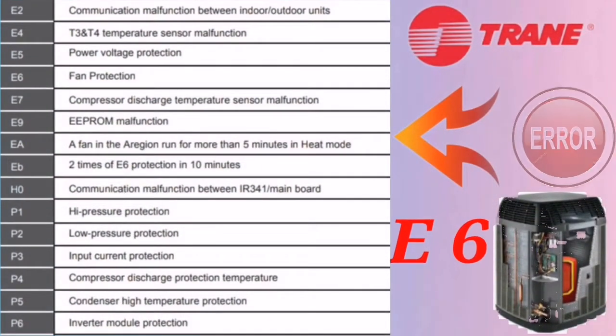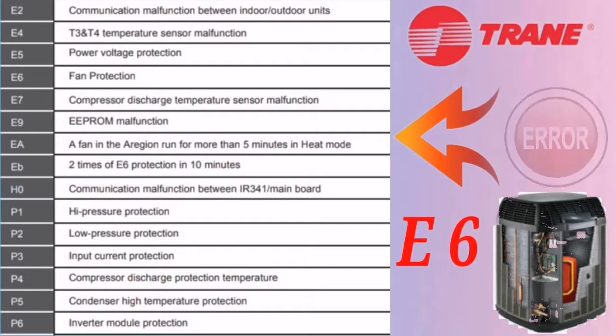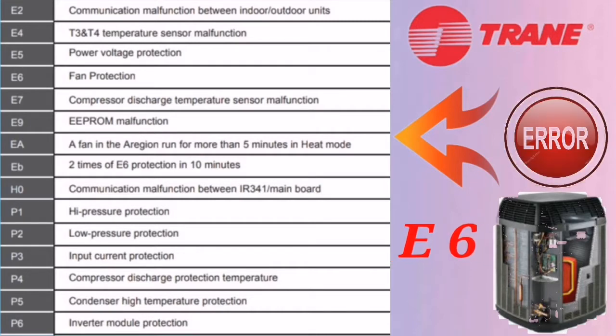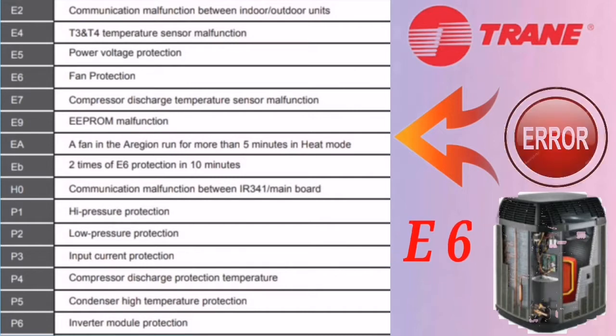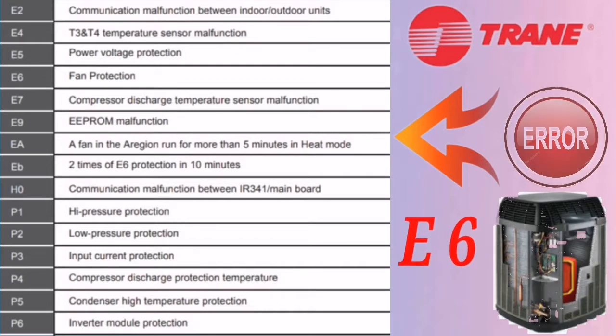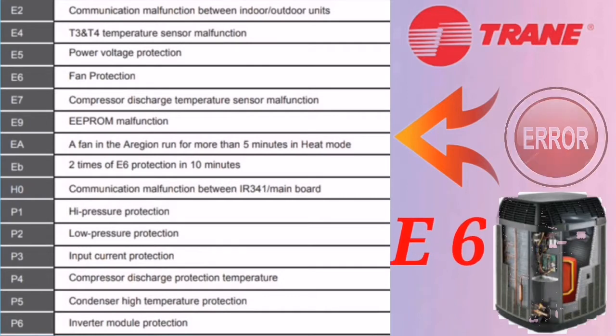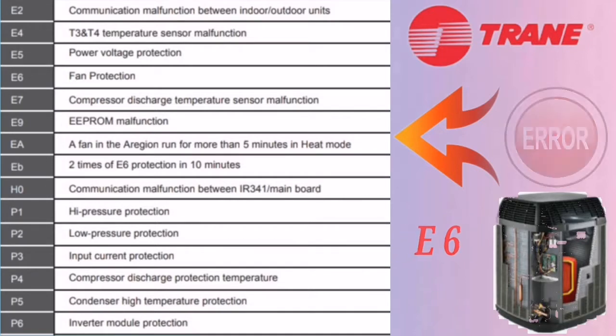The next error code is E6, which means fan protection. First, check the resistance of the fan motor — if the resistance is not okay, the fan motor is faulty and needs to be replaced. Then check if there is any obstruction at the fan air outlet and clear it properly. Also check if the fan blade is broken, as a broken blade can disbalance the rotation of the fan motor. Finally, check the output supply coming from the outdoor PCB to the motor to ensure it is good.